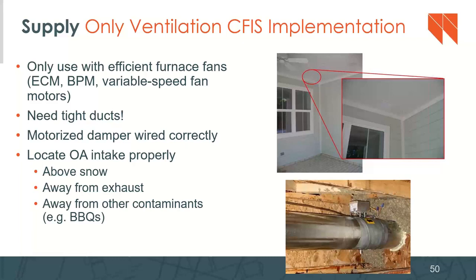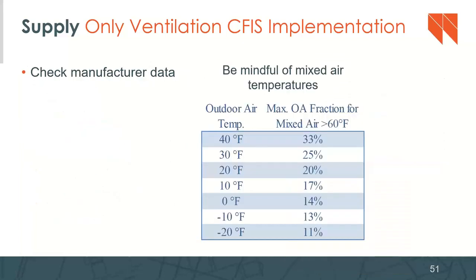This is another code thing as well, but you don't want to be bringing the fresh air for the home in next to the dryer or next to your kitchen range exhaust, right? That defeats the purpose. You're just recirculating that very moist air or polluted air or both right back into the home. This one was on a nice patio. I think when we were out there doing this testing, there was a nice grill set up right here. So, trying to keep it away from other sources of contaminants.